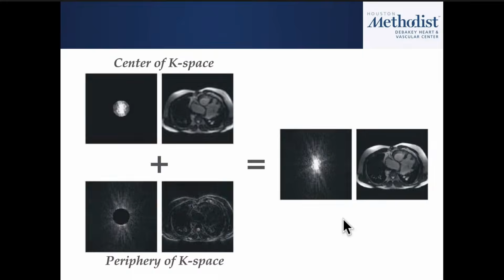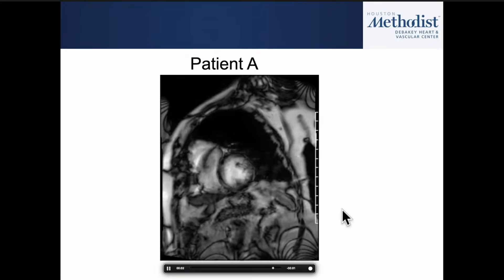Another important concept, and this applies for cardiac imaging, is that during the time of the lines of data that you utilize to form your image, if there are some errors or some differences occurring, then that can lead to a corruption of the entire image. So in this case, during the time that I'm acquiring my data, the patient's not holding their breath completely. And as a result, you can see it doesn't lead to just one localized area, but in fact, it leads to a distortion of the signal throughout the entire image. So that's what happens when you have a breathing artifact.